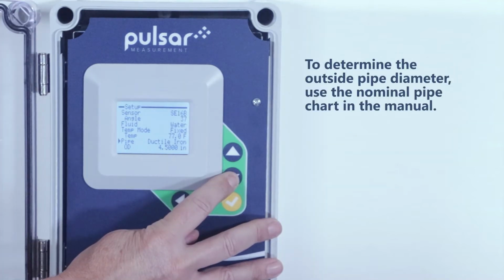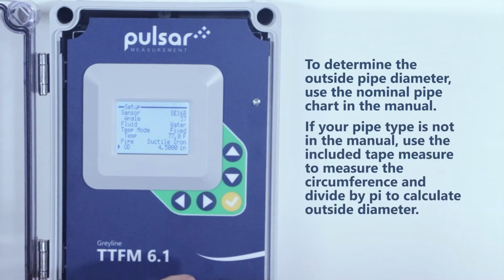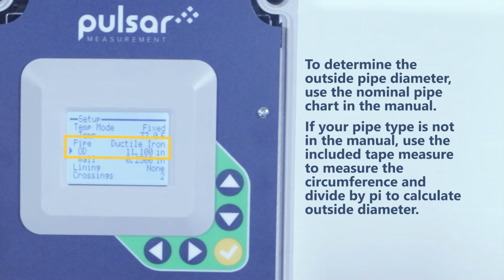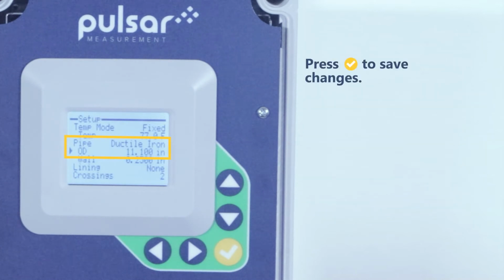To determine the outside pipe diameter, use the nominal pipe chart in the manual. If your pipe type is not in the manual, use the included tape measure to measure the circumference and divide by pi to calculate outside diameter. In our case, we know we're working with a Class 51 lined ductile iron pipe. According to the pipe chart, the outside diameter should be set to 11.1 inches. After this change is made, remember to press the check mark.